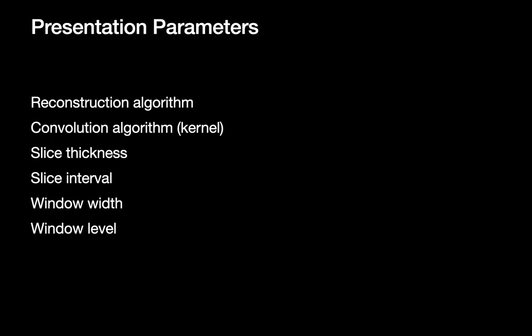Presentation parameters define the character of the images we create from raw data acquired after the scan. There are six presentation parameters to be familiar with: the reconstruction algorithm, the convolution algorithm (or kernel), the image slice thickness, the image slice interval, the window width, and the window level.